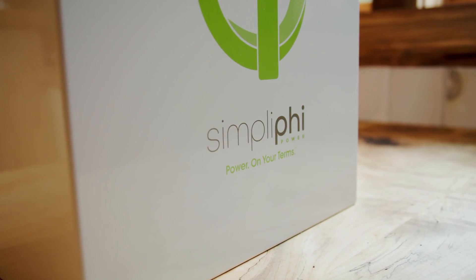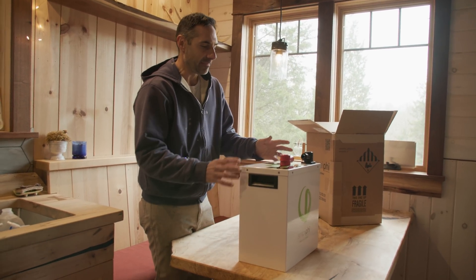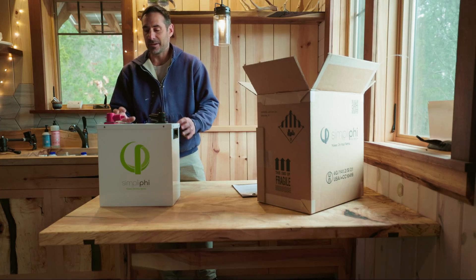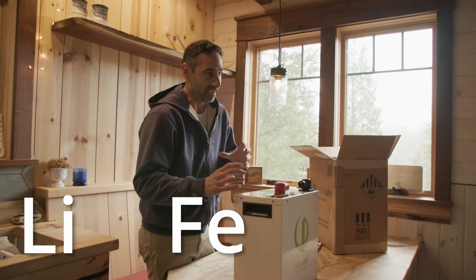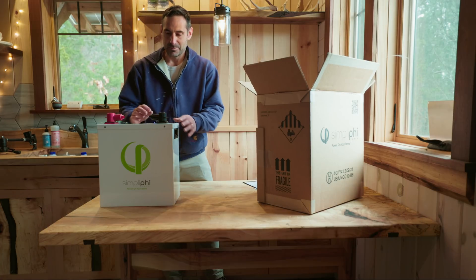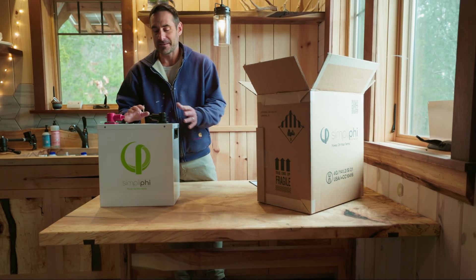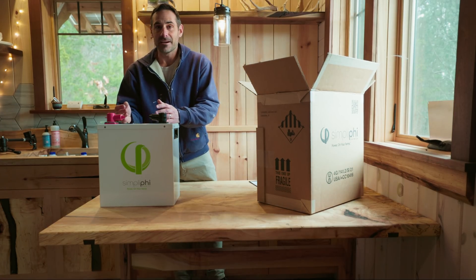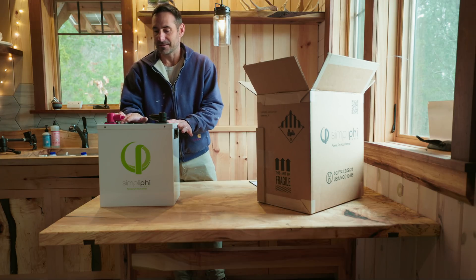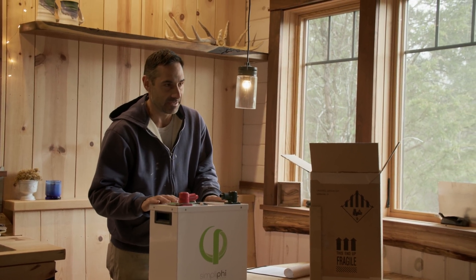Let me just talk a little bit about why I went with these batteries. These are in the lithium-ion family — they're lithium-iron, I-R-O-N, and they're LiFePO4 if you remember the periodic table of elements. Lithium-ion covers a broad spectrum of battery chemistries, so you don't want to confuse these with the type of lithium batteries that catch on fire, that you can't bring on airplanes. Those contain cobalt. These do not contain cobalt. Of all the lithium-ion battery chemistries, lithium-iron is definitely the safest.